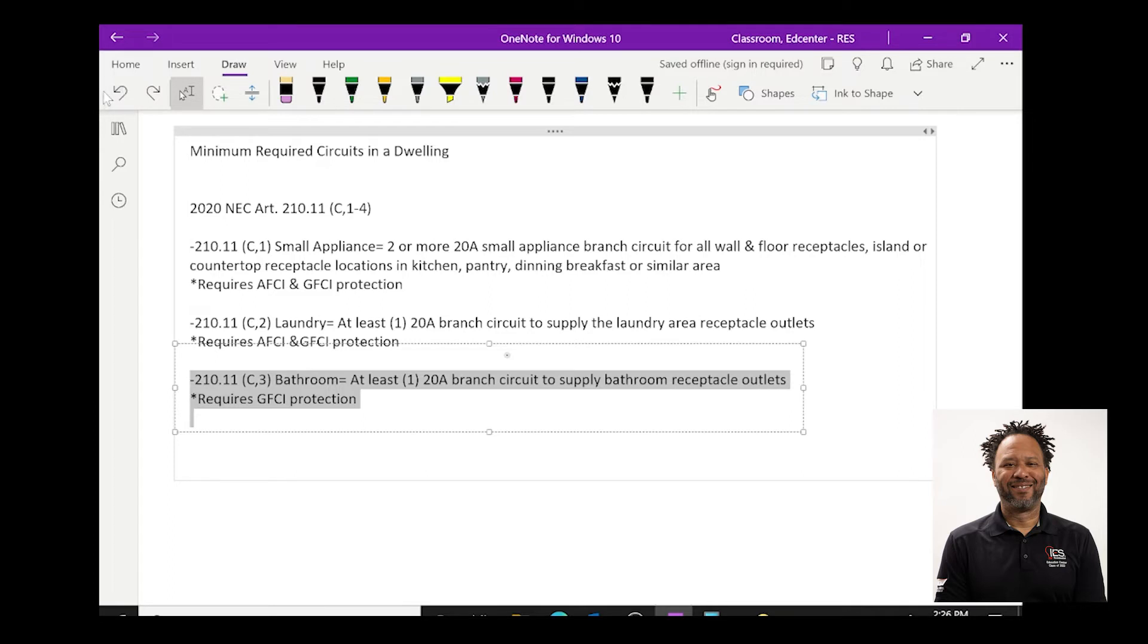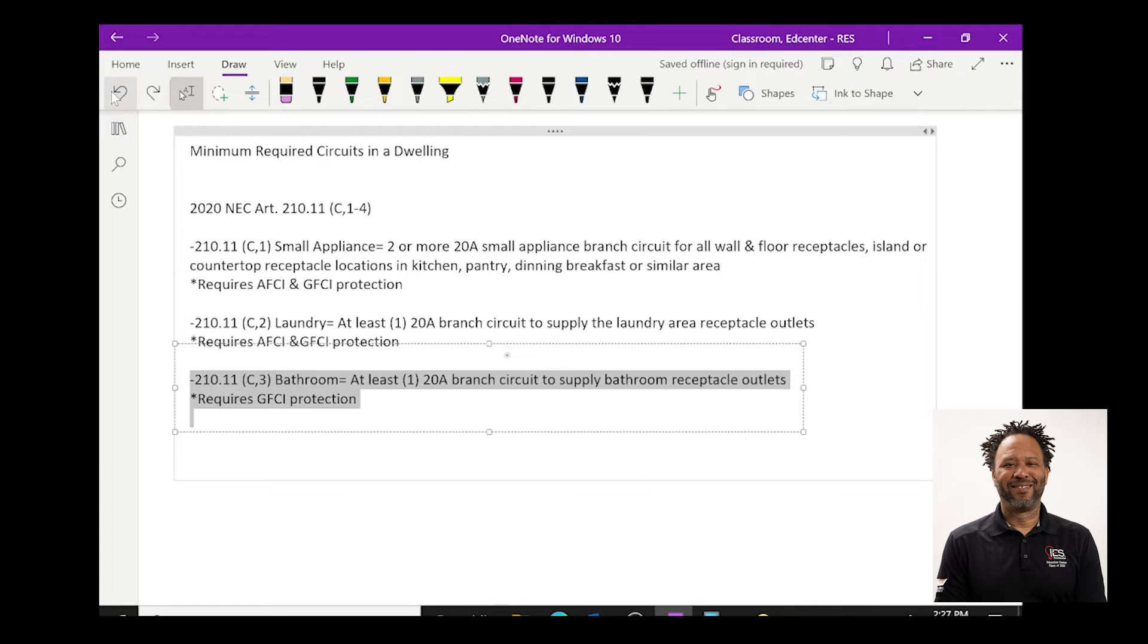Also, there is an exception in this bathroom article 210.11c3 that states that if you are using a bathroom circuit and it does not leave that bathroom and only serves that bathroom, you may also put switches and lighting on that circuit, but that is the exception. I invite you to read further into that.